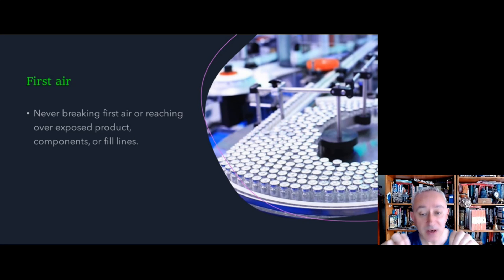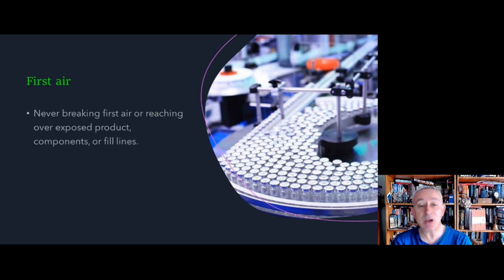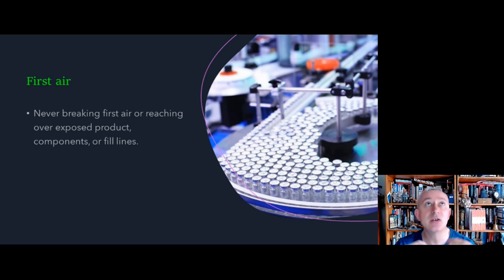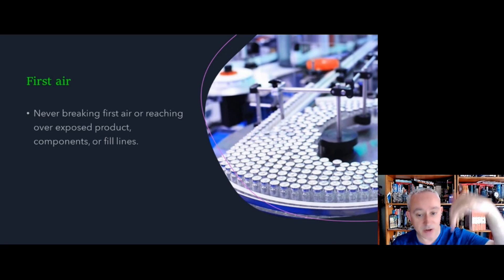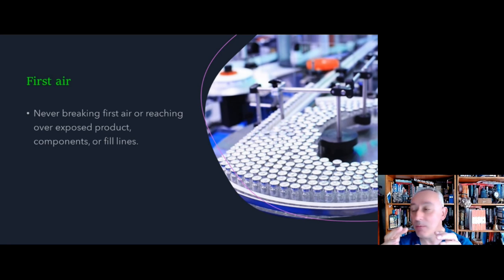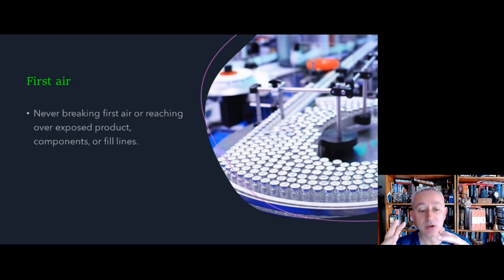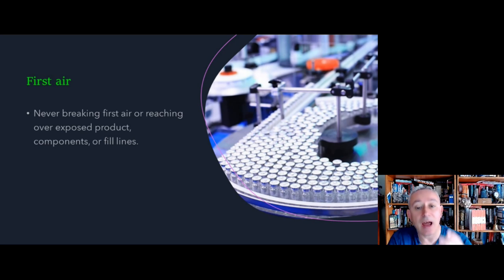First air is the principle of never breaking first air or reaching over exposed product components or the filling line. This is because first air is the last defense against contamination getting into the vial. First air is defined as the undisturbed air coming directly from HEPA filtration sources like unidirectional airflow. It's important to understand that many things can disrupt first air, and we need to avoid the airflow from becoming blocked or from things that might generate particulates due to their design, or anything that would create undue turbulence.